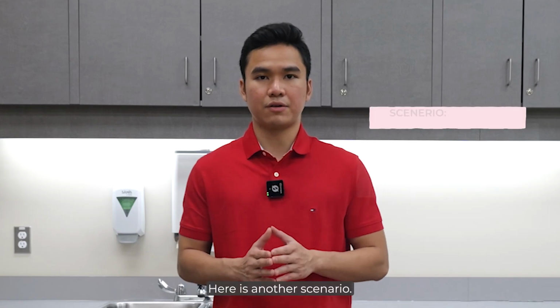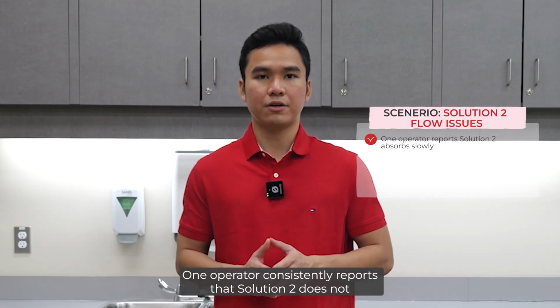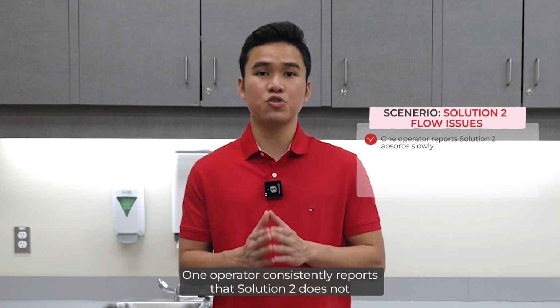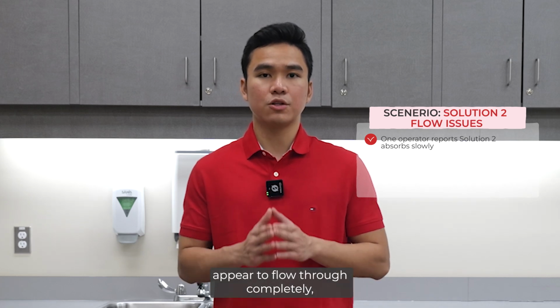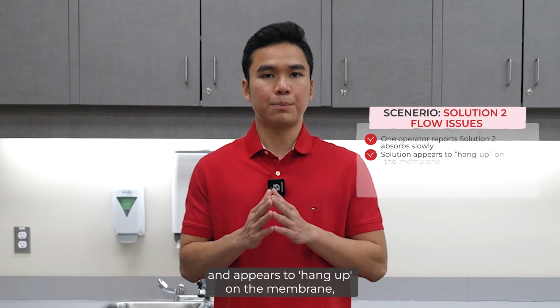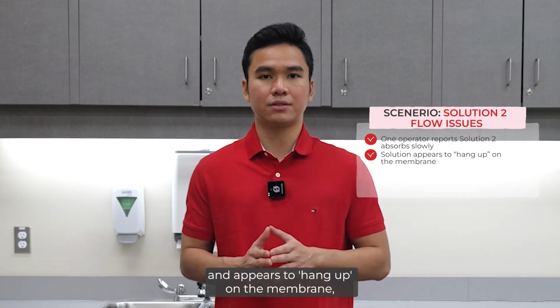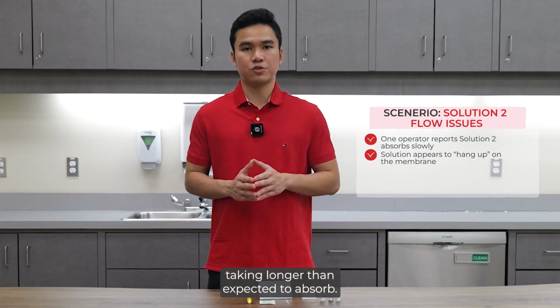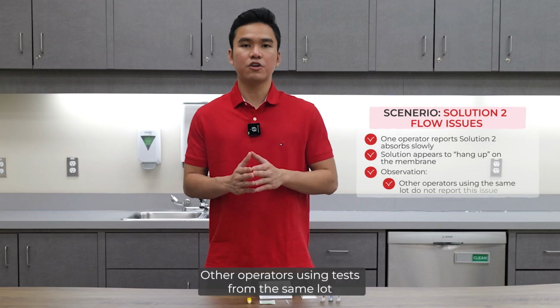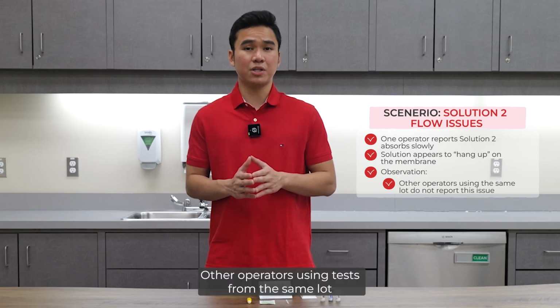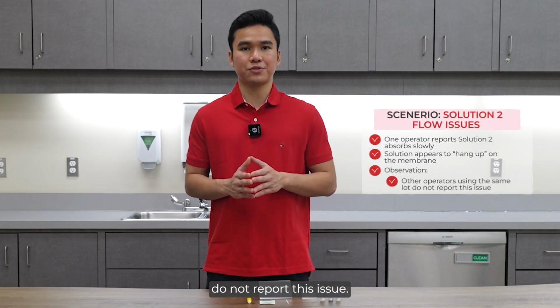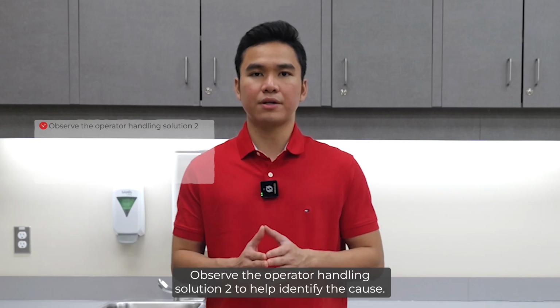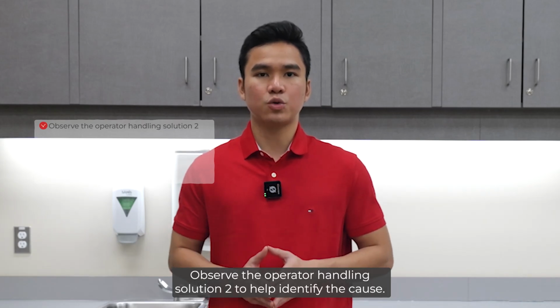Here is another scenario. One operator consistently reports that solution 2 does not appear to flow through completely and appears to hang up on the membrane, taking longer than expected to absorb. Other operators using tests from the same lot do not report this issue. Observe the operator handling solution 2 to help identify the cause.